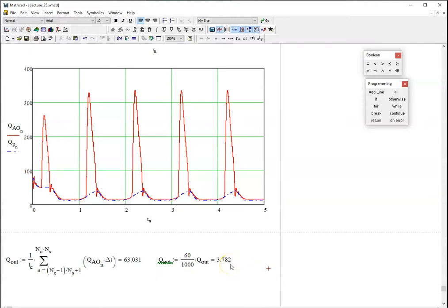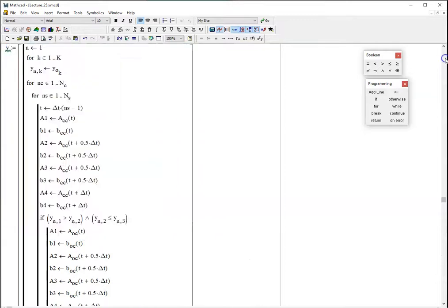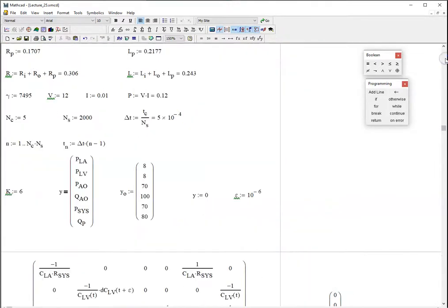That's definitely not enough flow — not enough pump flow. Actually, remember, this red line is not just pump flow, it's a combination of the two. This is not enough flow to satisfy the physiological demand when the systemic resistance is equal to 1. This person is walking, and might need about 5 liters per minute to withstand that level of activity. So we need a system that detects that and tells the pump to increase the level.